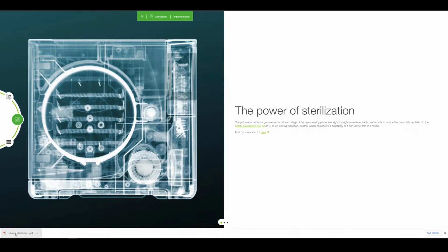What does it say? Okay, what does sterilization, steam sterilization mean? The reduction of microorganisms. Again, you can download these documents, save them on your computer, and read them later on. Here we have a quick description of our European standards, on B, N, and S type cycles. I don't want to develop too much information about the prion protein, which requires an extended sterilization plateau.